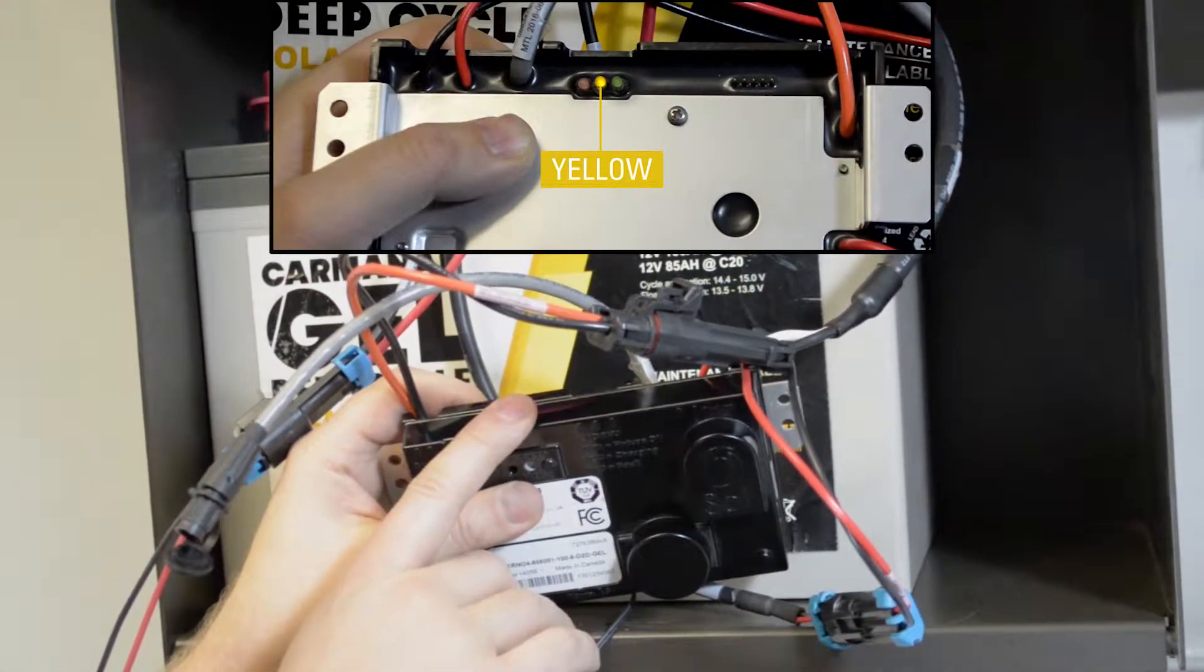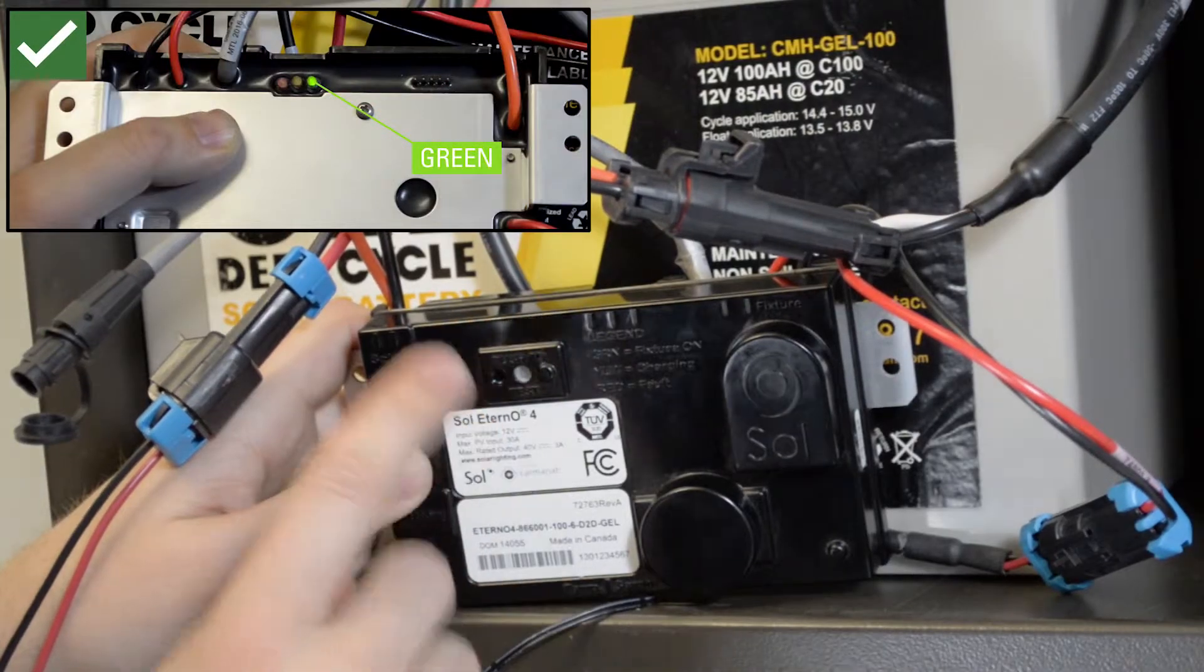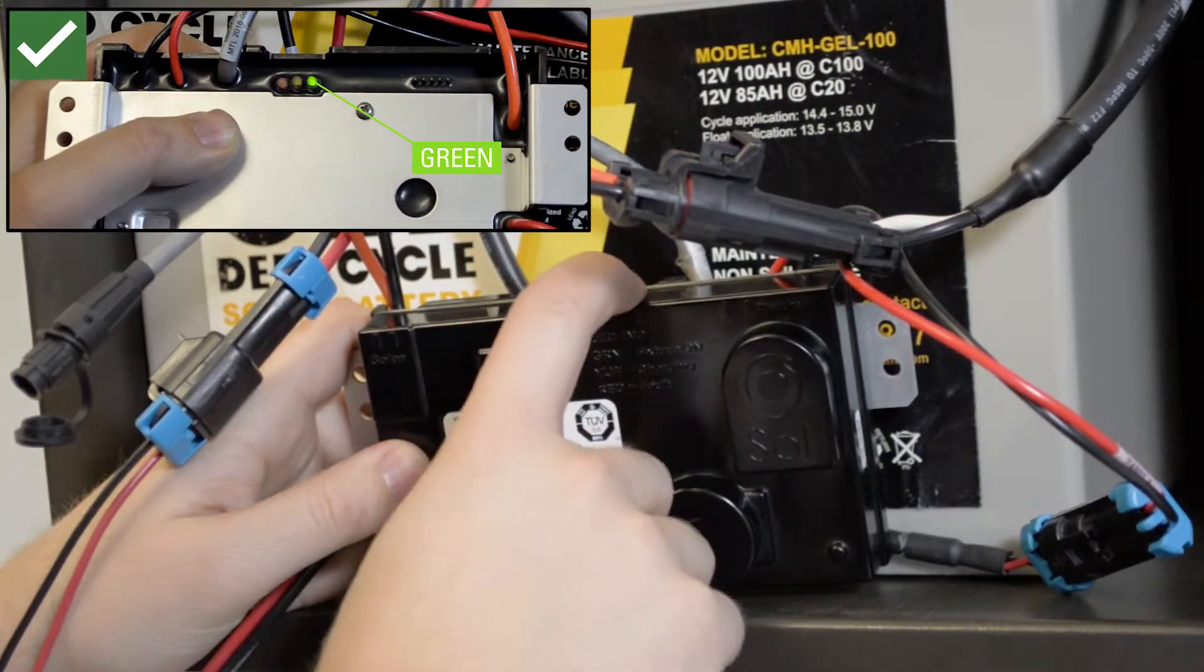During the daytime you should only see the yellow light indicating that it's in charge mode. If you don't, you may have issues with the panel connection, and we'll show you how to check that in a bit. When you push the test button, the fixture should turn on and you should see a green indicator light.